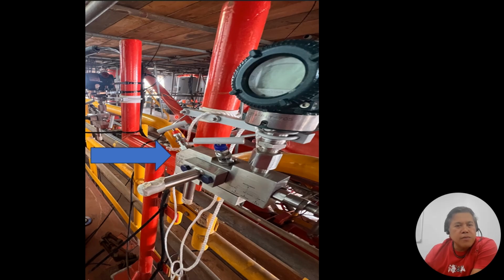Basically this kind of transmitter, as you can see from this side, has a small bar holding the transmitter. And if you have a manifold, and when you are providing the valve here, it's too heavy and not supported, it will damage our transmitter. And also here our manifold is touching this stanchion. So this is part of the design phase, and how we prepare our stanchion and how we order our instrument transmitter.